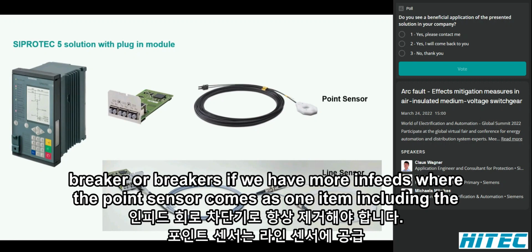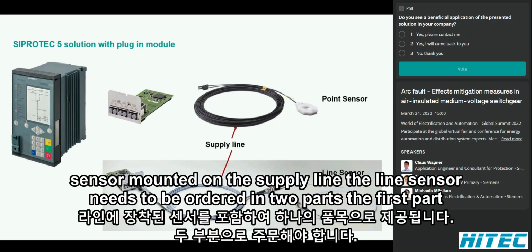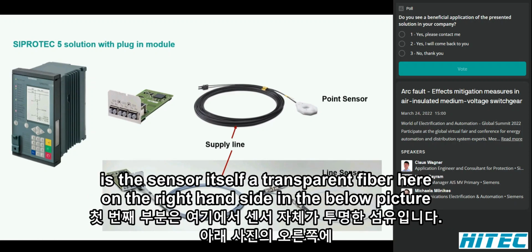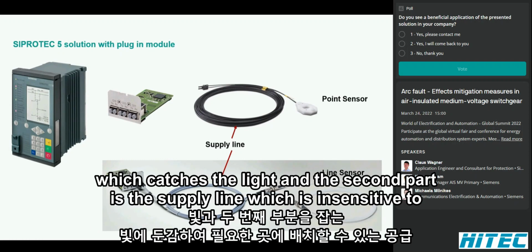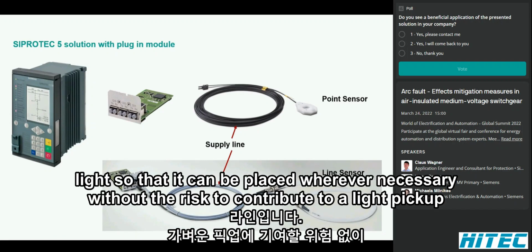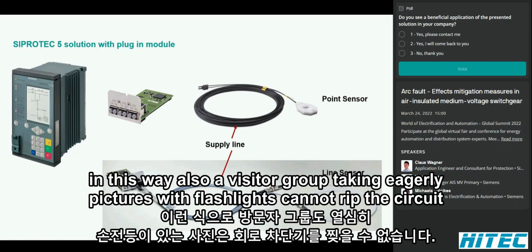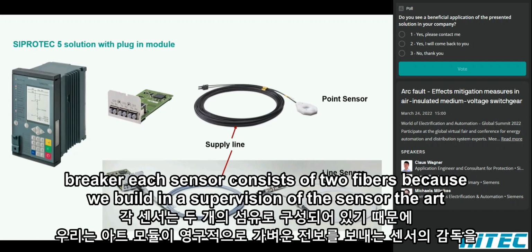Where the point sensor comes as one item, including the sensor mounted on the supply line, the line sensor needs to be ordered in 2 parts. The first part is the sensor itself, a transparent fiber, here on the right-hand side in the below picture, which catches the light, and the second part is the supply line, which is insensitive to light, so that it can be placed wherever necessary, without the risk to contribute to a light pickup. In this way, also a visitor group taking eagerly pictures with flashlights cannot trip the circuit breaker.